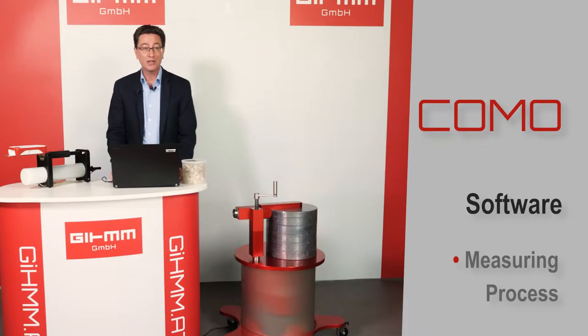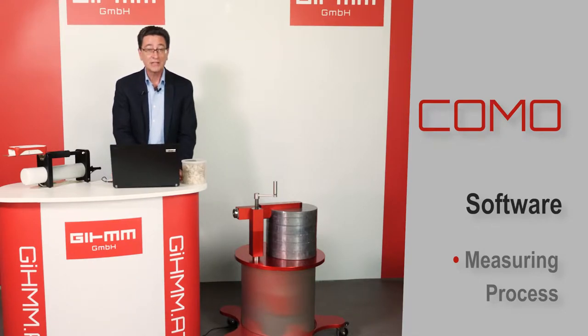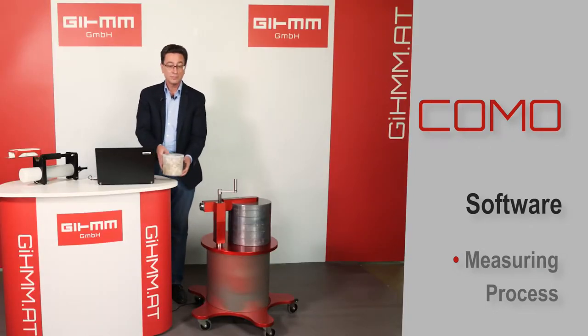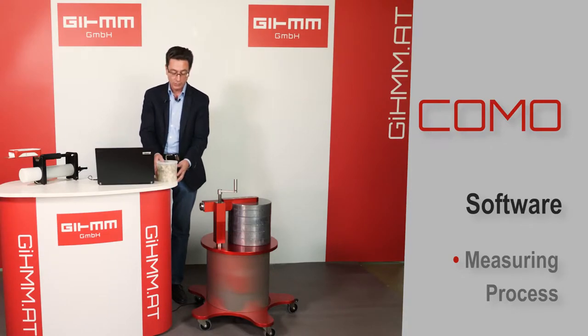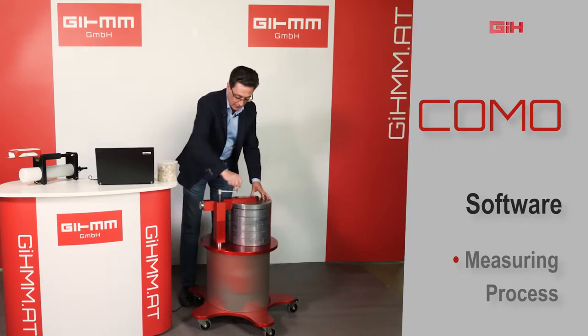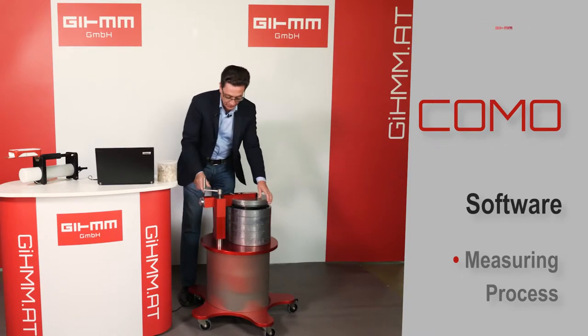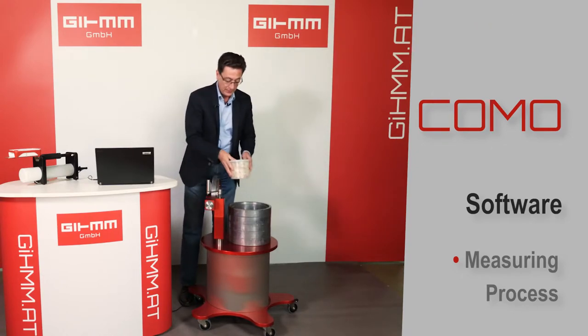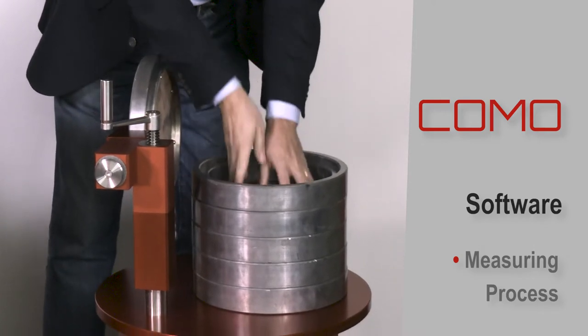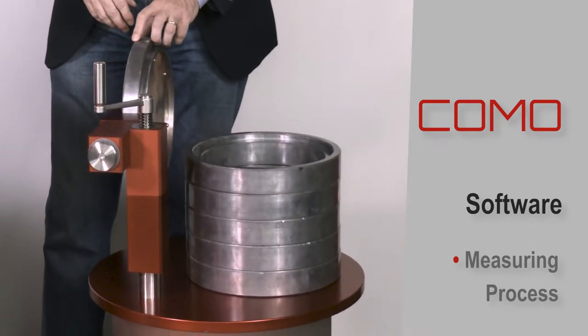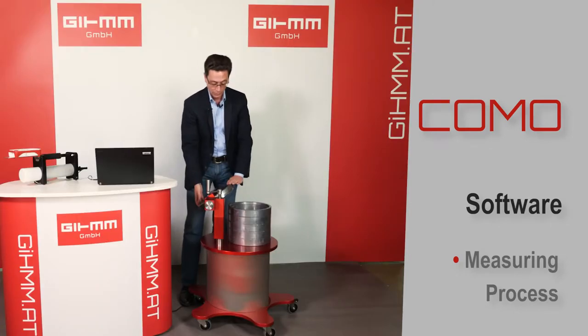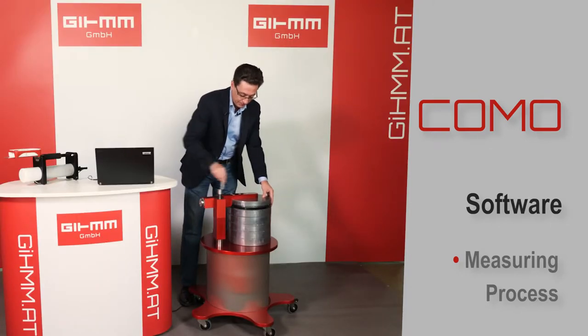Now it's time to measure our sample. We simply press the button sample measuring. Again, a pop-up window appears asking us, make sure your sample is inside the measuring chamber. Of course, I've taken it out before, so I have to place it inside. We open the top of our measuring chamber, shove it aside, take our sample, place it inside on top of our gamma spectrum detector, GSB02, and again close the cover.